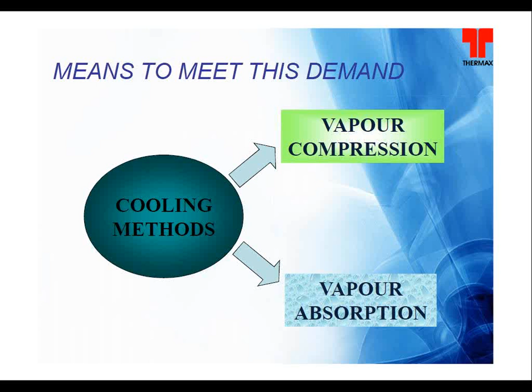Now I will just tell you slightly about the types of vapor absorption machine. Based on the heat input, we can define it in two categories majorly. One is direct fired and second is the indirect fired. In indirect fired, there are categories like hot water and steam driven. Apart from that, there are direct exhaust gases from gas engine, gas turbine or oven recovery gases, which will be more than 150, 200 degrees centigrade. This is all in the indirect fired mode.